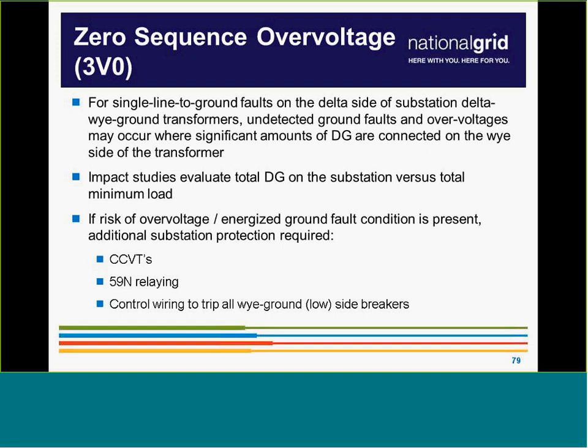So we're doing two things with that 3V0. We're making sure that we're not overvolting equipment for too long, and we're also making sure that we're not leaving ground faults on the transmission system forever, to potentially become a safety issue where somebody walks up to the line.